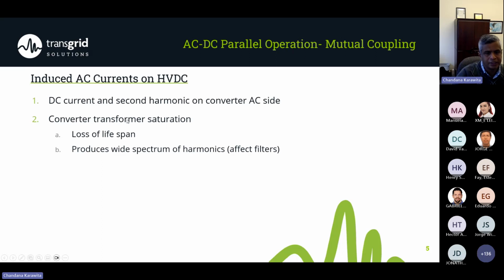Because of the DC current and the second harmonic, that will add additional losses as well as contribute to the total harmonic distortion. Both of these issues should be resolved, otherwise we will see loss of lifespan of the transformer. And if we have filters with the HVDC, this will affect the filter performance as well. So these are the challenges with steady state induced AC currents on the DC.